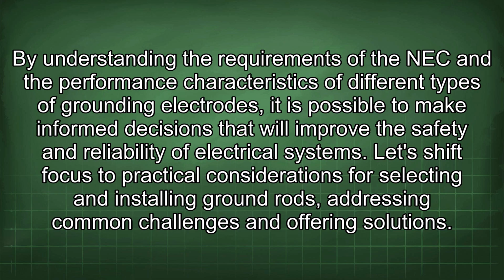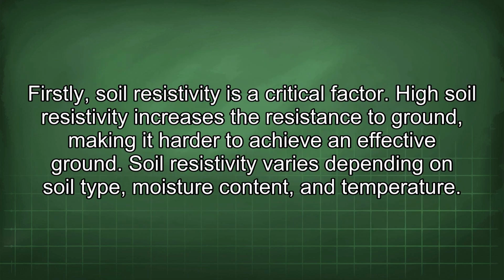Let's shift focus to practical considerations for selecting and installing ground rods, addressing common challenges and offering solutions. Firstly, soil resistivity is a critical factor. High soil resistivity increases the resistance to ground, making it harder to achieve an effective ground. Soil resistivity varies depending on soil type, moisture content, and temperature.